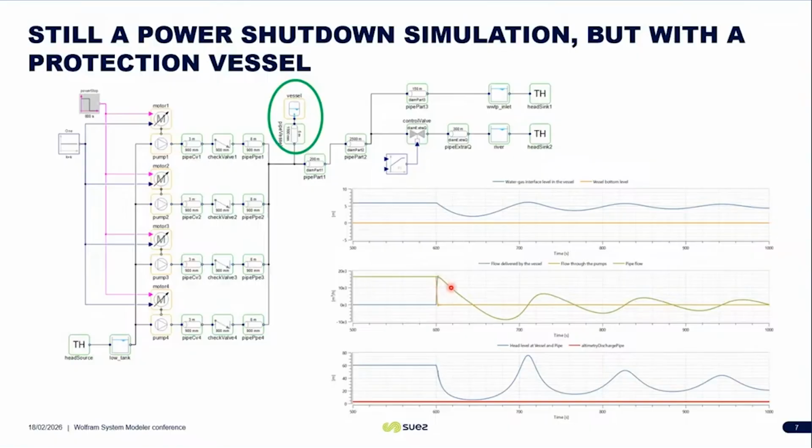At the same time, we can see the air expansion progressively reduces pressure and flow, but this is controlled in a gradual manner. So we can see the flow rate going down slowly, avoiding a sudden depressurization of the system. The vessel behavior on the first plot: we can see that the liquid level decreases as water is supplied, and then the system reverses and the vessel refills again. Well, this is a cyclic movement after the pump stop.